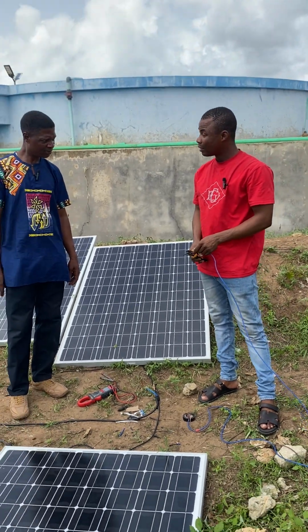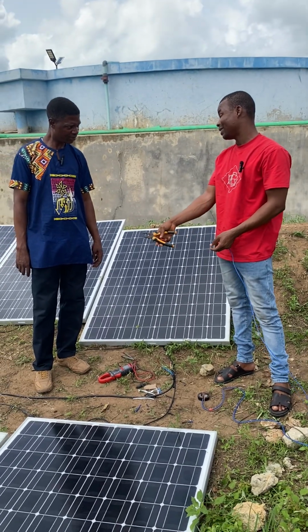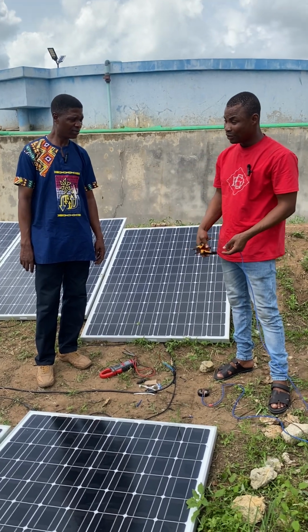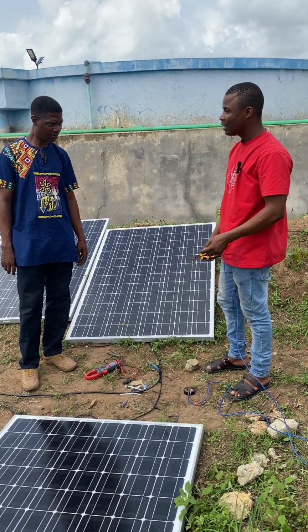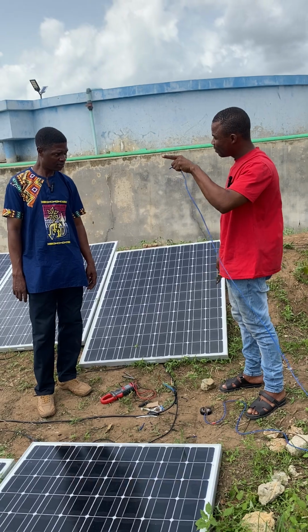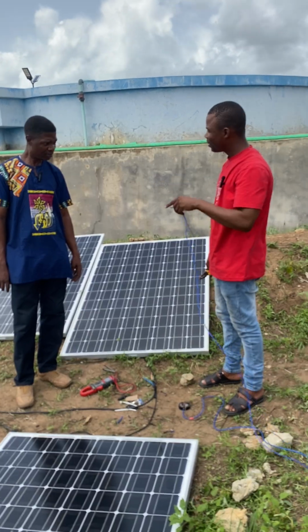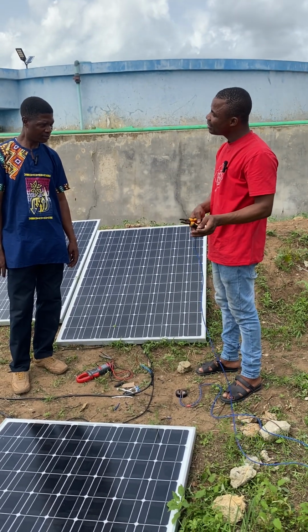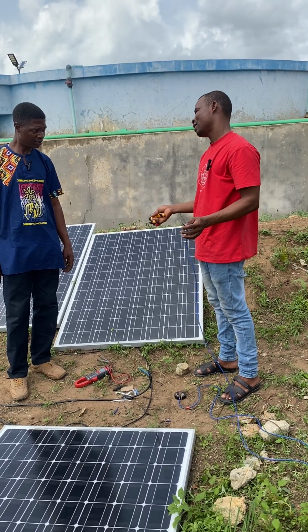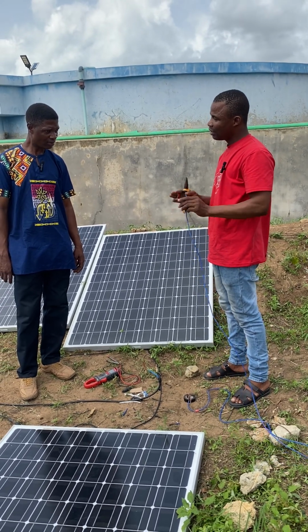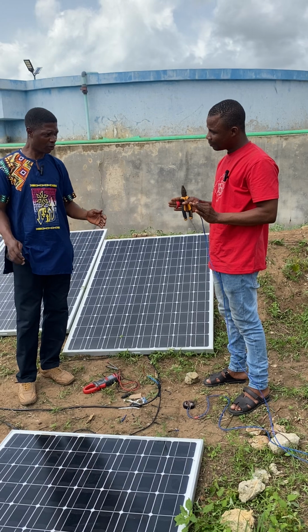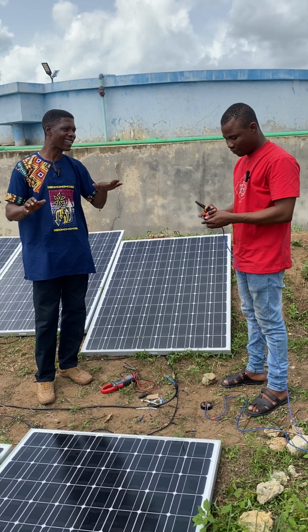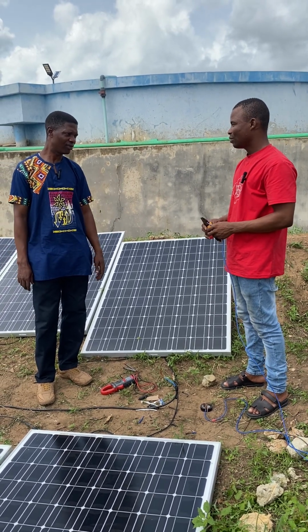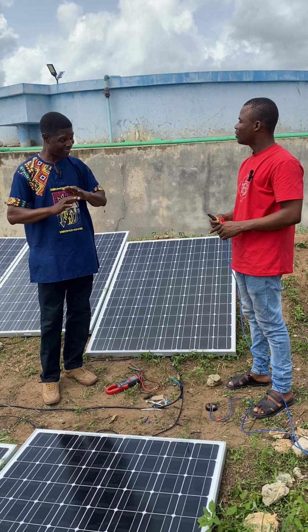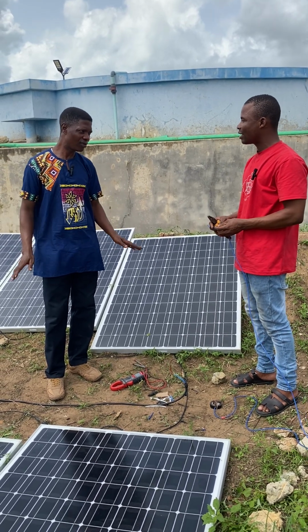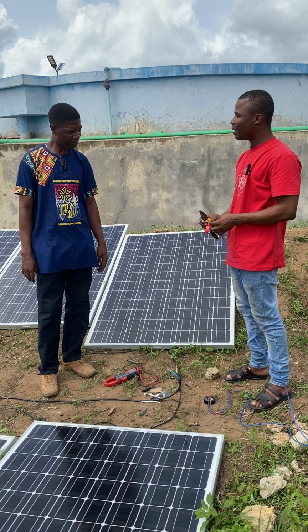For you to do a solar panel, it's just like what we do, we calculate the power rating. What's the power rating of that pumping machine? What's the power rating of the solar panel? Now, what is the minimum voltage of the pumping machine, from 380 to 750? The VOC and the VDC. So you understand that first. So that information is needed before you start any installation. Failure to understand that is very hazardous. It can damage someone's house.